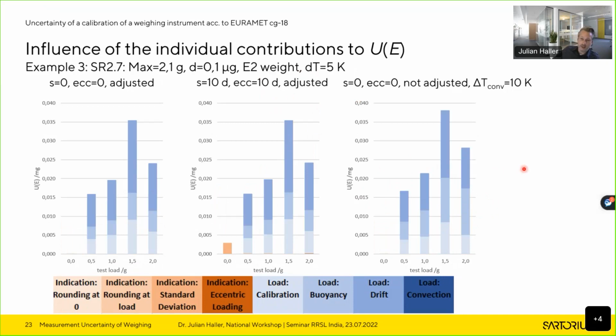And actually, just the opposite example, if you consider an ultra micro balance, so a maximum of 2.1 grams and a scale interval of 0.1 micrograms, it more or less doesn't matter what you do. So you see, I assumed really big standard deviation and eccentricity deviations here. But whatever you do, you see that the uncertainty is dominated by the uncertainty of the reference weight. Which just means, if I state that positively, this balance is too good for the weights. Or if I state it negatively, actually the weights are not good enough for that balance. Because whatever you do, the calibration uncertainty actually is the uncertainty of the reference weights.